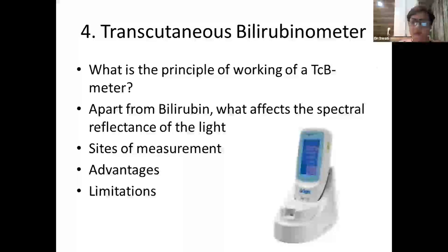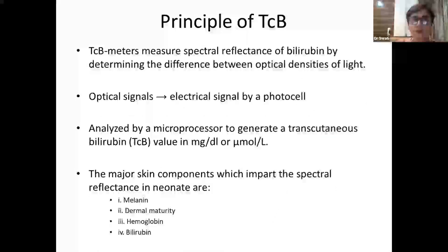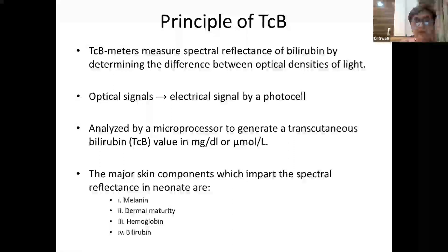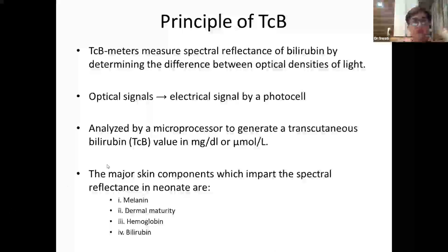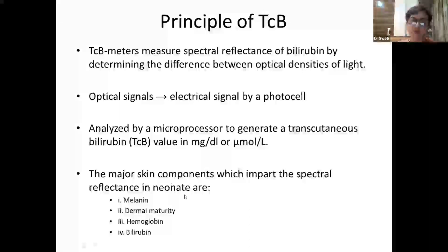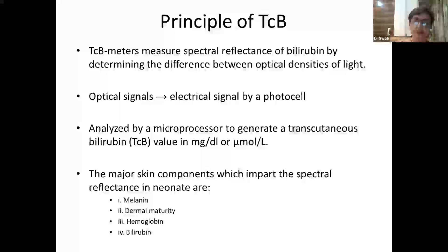For preterm babies there is a different device called JM105. Transcutaneous bilirubinometers measure the spectral reflectance of bilirubin by determining the difference between optical densities of emitted light. These optical signals are converted to electrical signals by a photocell and processed by a microprocessor to generate a transcutaneous bilirubin value in mg/dL or micromoles/liter. The major skin components that impart spectral reflectance in neonates are melanin, dermal maturity, hemoglobin, and bilirubin — melanin and dermal maturity can interfere with readings.